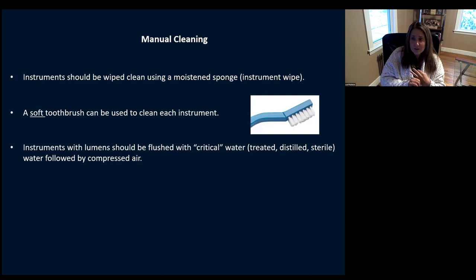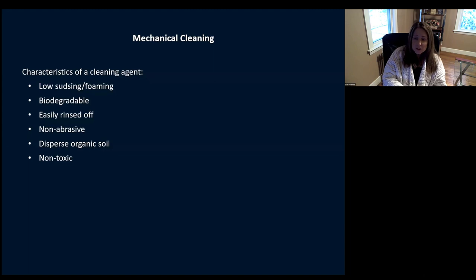Those fluids in lumens can then get sterilized, brought to the next patient, and get squirted out — this is how we have issues. Then you have your mechanical cleaning: sonic machines, a regular tabletop sonic machine, or a large washer-dryer. When choosing your detergent and cleaning agent, make sure it has low foaming, is biodegradable, can be easily rinsed off, is non-abrasive, can disperse organic soil, and is non-toxic. Check the manufacturer's instructions on them — especially make sure it's very low sudsing and low foaming.